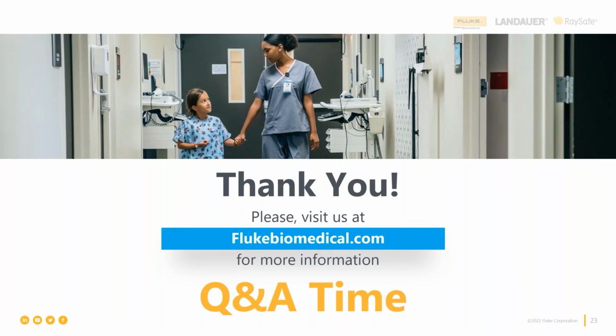Okay, next question. How do you test the electrical safety for medical device class 1 devices if you're unable to find the ground point on the surface of the machine? You cannot. Here's the test that you cannot do if there's no accessible protective earth or ground. Even if you have a 3-prong power cord, you're not supposed to go get a ground from someplace else. The ground has to be provided on the medical device.